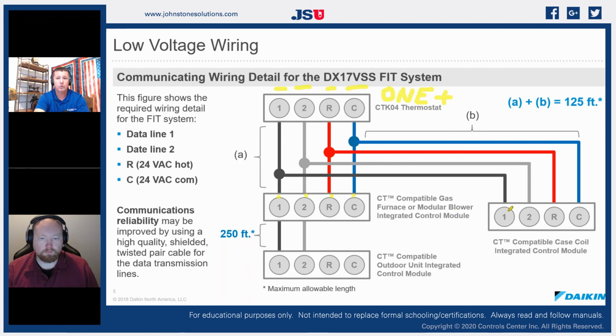On the 1+, or on the Daikin FIT, we're going to add that cased coil right on this gas furnace. So we've got our 1, 2 communicating, and then our RC for 24 volts AC. And that's going to control the control board. And then the separate transformer that we installed, that's going to run the electronic expansion valve. It's a lot of current running those windings, so we had a separate transformer.